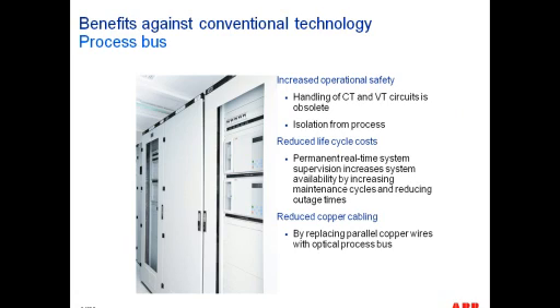So from a process bus perspective, there's definitely 3 benefits that need to be highlighted, and one is the increased operational safety due to the isolation of the galvanic connections onto the relay, which are now in the form of fiber optic cables, reduced life cycle cost. You have a permanent real-time system supervision, which increases system availability by increasing maintenance cycles and reducing outage times. What this means is that you're going to have redundant electronic parts to your sensors. You're able to monitor whether the sensors have failed, whether the merging unit has failed, and whether your protection relays have failed or not. So the capability of monitoring the device up to the primary sensors is certainly increased. And then obviously there's the savings in regards to copper cabling.